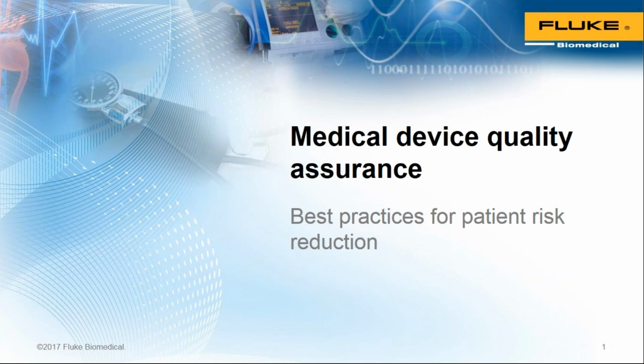But basically the answer is this, that everywhere else after the medical device has been delivered to the healthcare facility, we're operating on IEC 62353, which is much closer to ANSI NFPA 99. Each of those organizations, ANSI and NFPA 99, have a little bit different point of view about electrical safety. And recently, the NFPA in the US had said, you know what, we've been testing this for a long time, nothing's changing. So, you know what, kind of just don't worry about it. You can just test it when you're ready. Not a really good idea, but also the requirements for that earth bond test are much smaller, as small as 200 milliamperes to do the test.